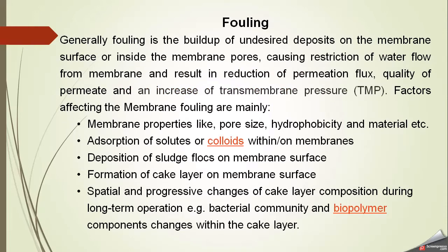Fouling is basically the buildup of undesired deposits on the membrane. Impurities present in the water deposit on the membrane surface or inside the membrane pores. When these undesirable substances deposit on the membrane, they cause restriction of water flow, resulting in a reduction of permeation flux, quality of permeate, and an increase of transmembrane pressure.